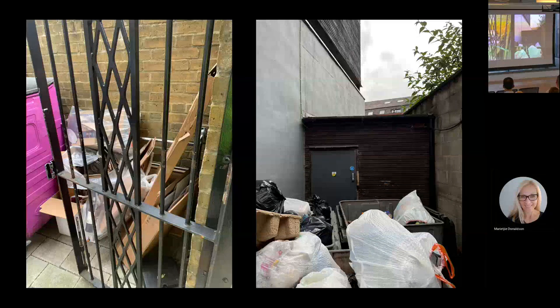In a real-world application, does IntelliClad really work? The answer to this is yes. We know this because one of our installations in London actually had a bin fire. A smoke detector in the bin store went off, and exactly 4 minutes later, smoke had travelled into the cavity and the first IntelliClad detector installed in the combustible facade was triggered. The system worked as it was designed to do.